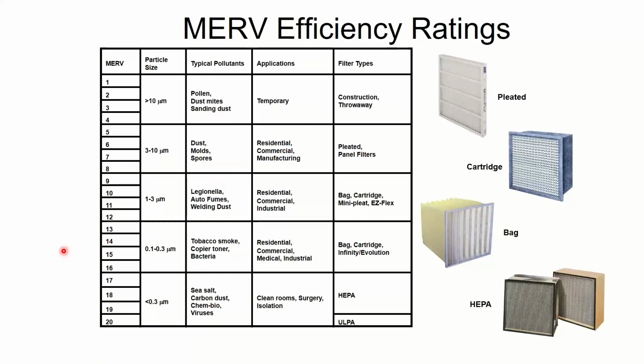Filters are tested with ASHRAE Standard 52. This is what we call the MERV rating standard. 52.2 specifically. There's an old 52.1. You don't want to get involved in that. That's been obsoleted for 20-plus years. It was replaced by the new ASHRAE standard. By new, I mean 20 years old. And that's where the MERV rating system comes from.